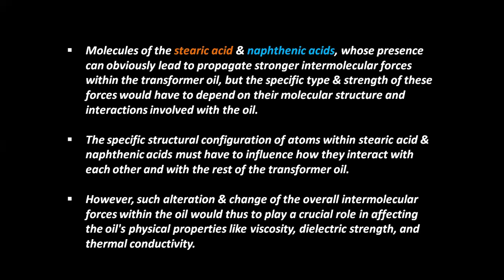The specific structural configuration of atoms within stearic acid and naphthenic acids influences how they interact with each other and with the rest of the transformer oil. Such alteration of the overall intermolecular forces within the oil would play a crucial role in affecting the oil's physical properties like viscosity, dielectric strength, and thermal conductivity.